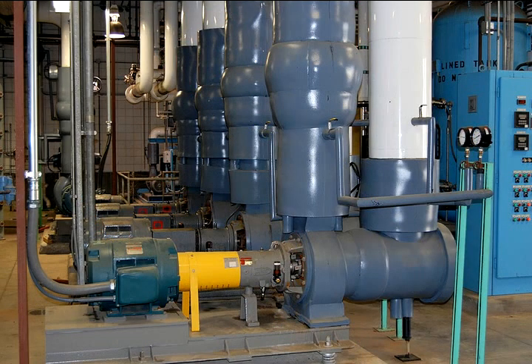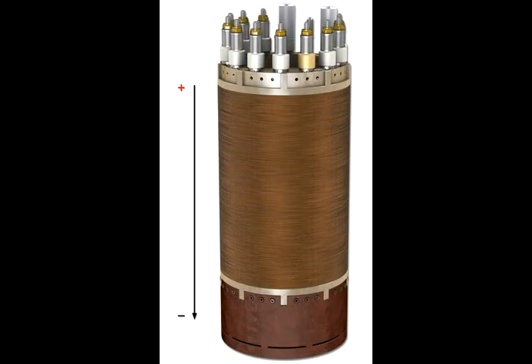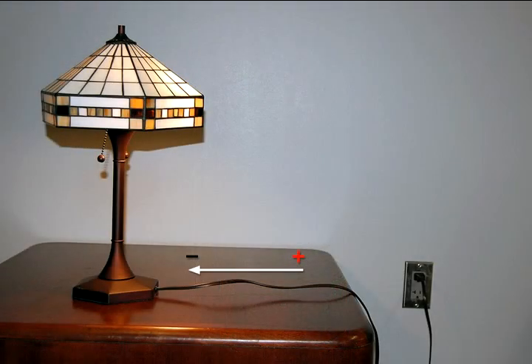Now in the control room we supply our magnets with up to 720 volt DC power, DC meaning direct current, electricity flows in one direction. If we used AC power on our magnets, which you would have coming out of your wall, the poles on the magnet would be flip-flopping 60 times a second and that really would not provide the stable field that the users need to do their research.